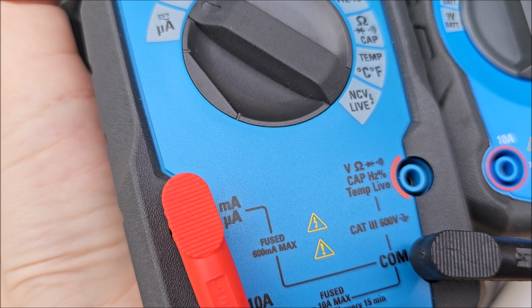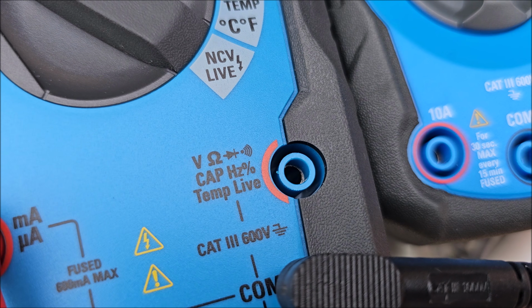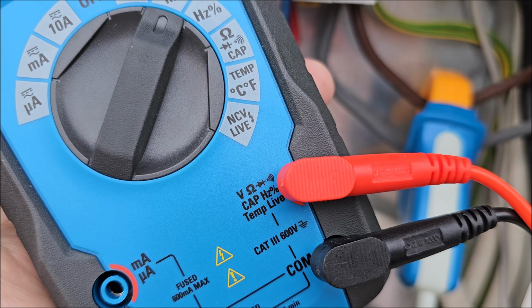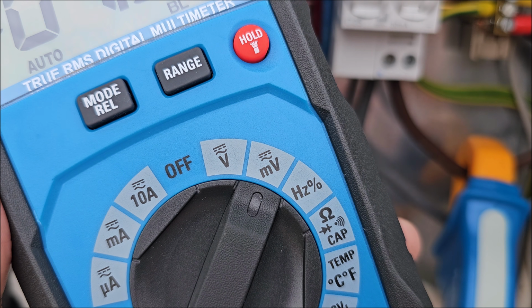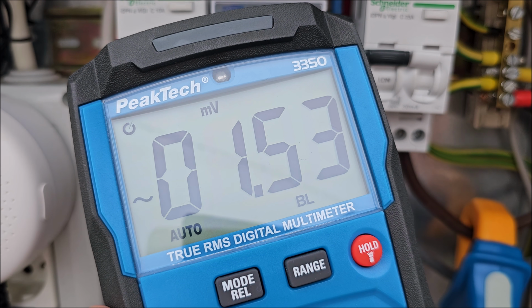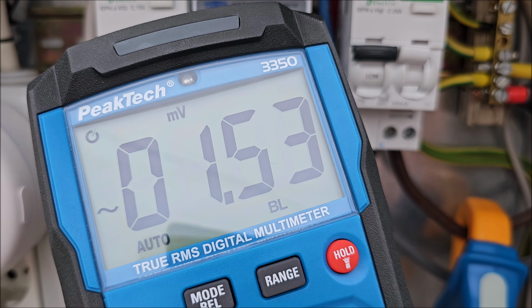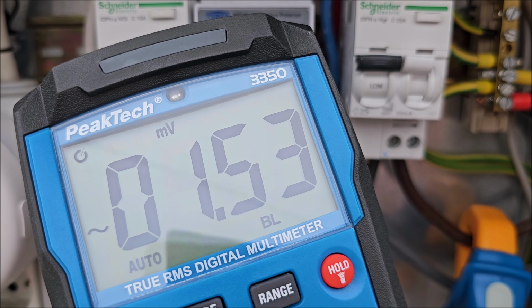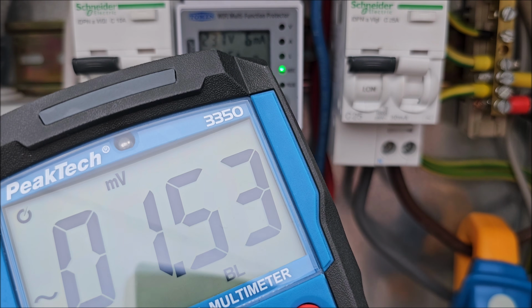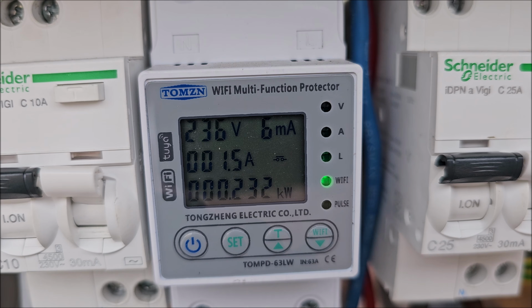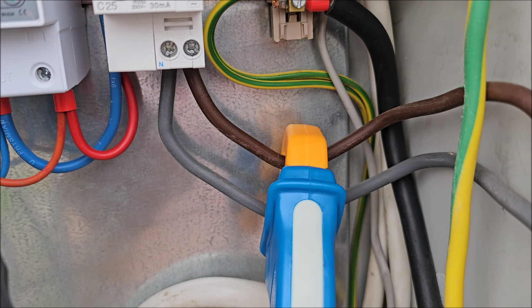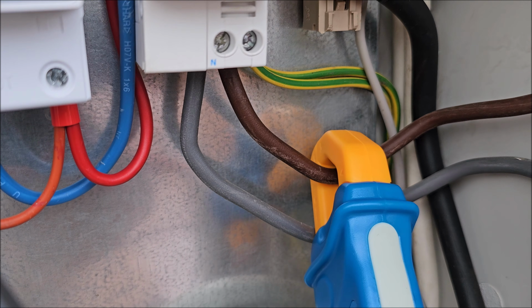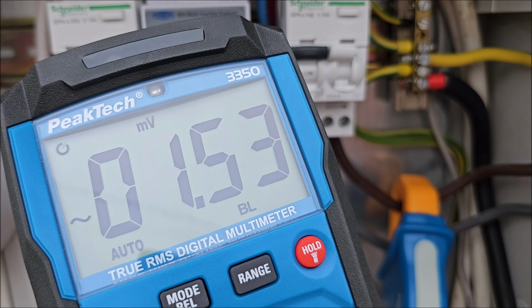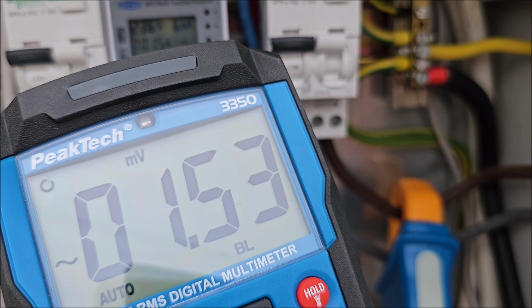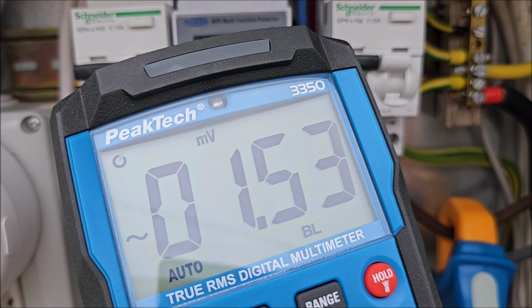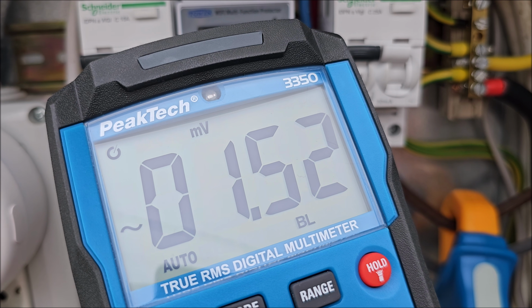We are in the wrong port. We need to be here. And now we are in the correct port on the correct reading type. 1.53 millivolts. That means 1.53 amps. Exactly what this guy is also saying. And I could just clamp over the live wire, over the neutral, you get the same thing, doesn't matter, and get the reading extremely easily.